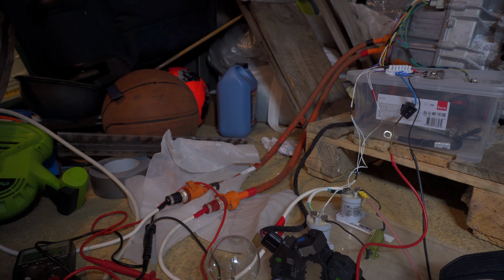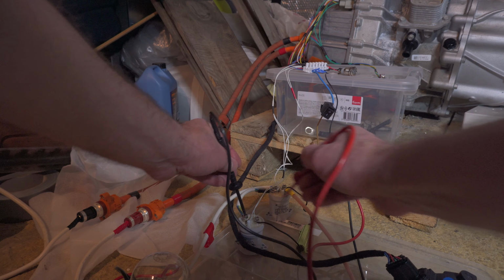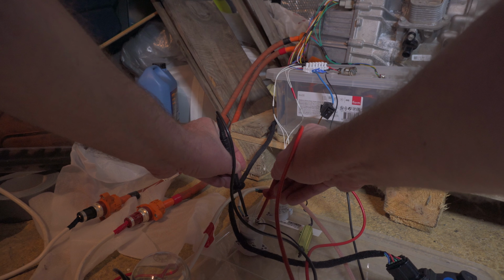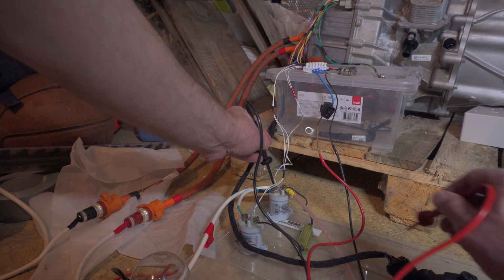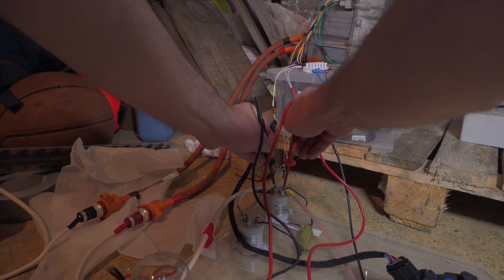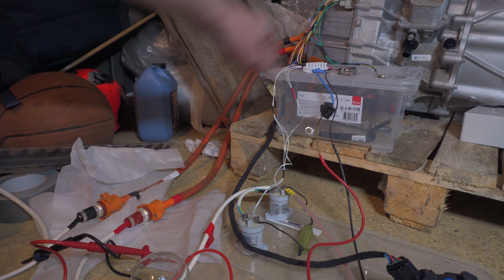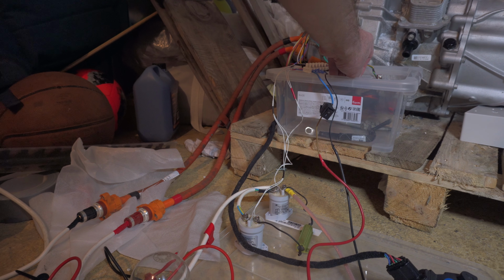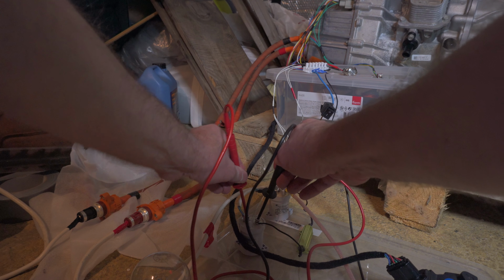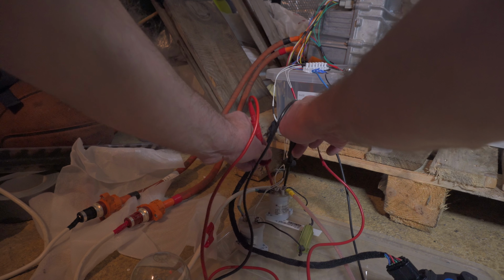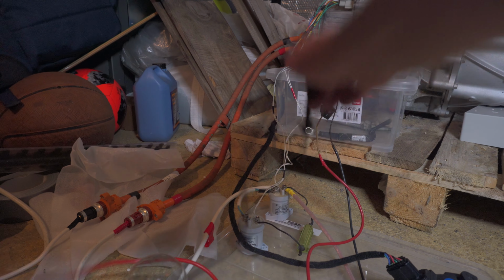You can see that the bulb is flashed. Pre-charge is closed and main contactor is open. If I press the start button, pre-charge should open and the main should close, but they both closed.